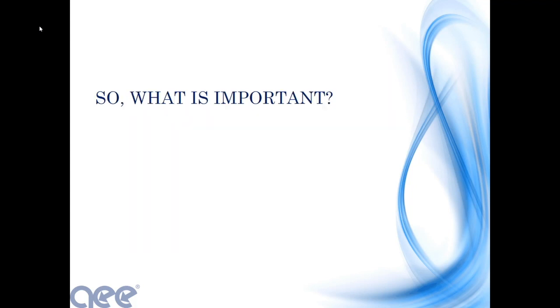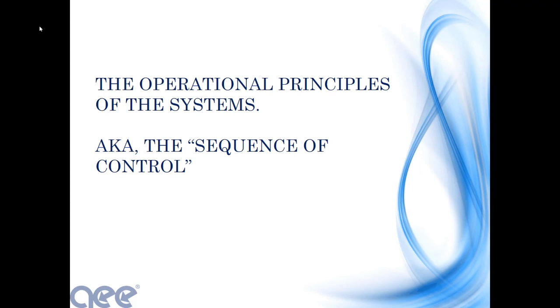So, what is important? In my opinion, what's important is the operational principles of the systems that we're controlling. And we generally call that a sequence of control or a sequence of operations. If you're doing controls, it's important for you to understand that. If you're directing your controls vendor, it's even more important. Because if you're going to do the commissioning, you want to see the system function and accomplish the goals that you set out for that system.